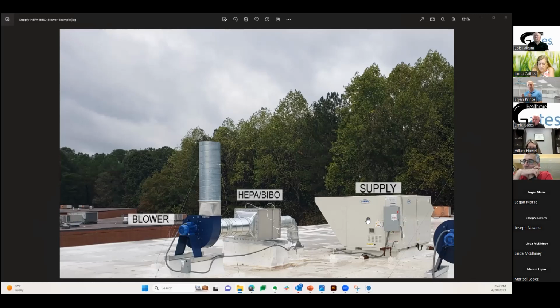And if your clean room's out of spec and people can't produce product, that is called a non-revenue generating activity. So yes, the price tag's going to hurt, but do you want your clean room to have a 99% uptime? So I would ask you to go back and look at all your temperature and humidity logs for the past year and see what's really happening at certain times of the year.